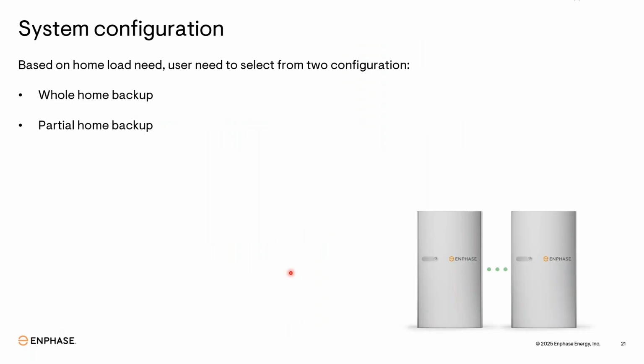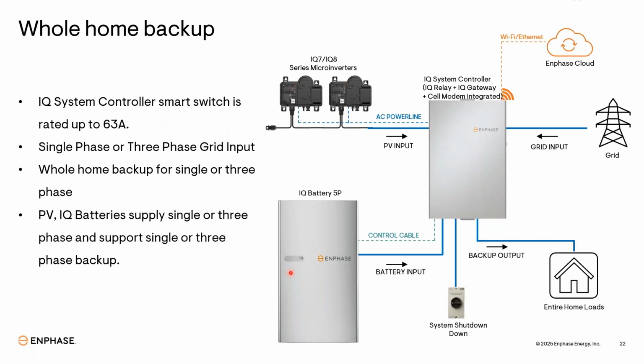Now moving towards the system configuration. We have two types of system configuration: the whole home backup and the partial home backup. Whole home backup, as the name suggests, means you are going to back up your complete home. Our IQ controller supports 63 ampere per phase, so it's like 14.5 kilowatt per phase. It's something near about 44 kilowatt for the whole home. For a residential whole home, 44 kilowatt is enough power.